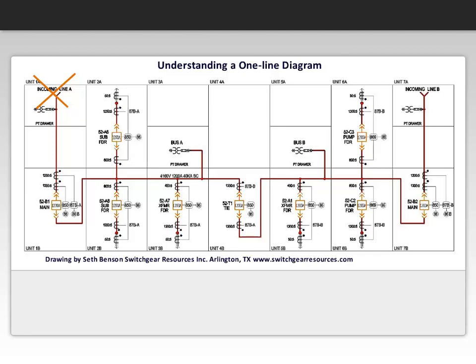However, with this option, the tiebreaker could be closed, allowing the feeder breakers in structures 2 and 3 to receive power from incoming line B. The same process can be accomplished in the event that power is lost from incoming line B. The changeover can be carried out by maintenance personnel manually.